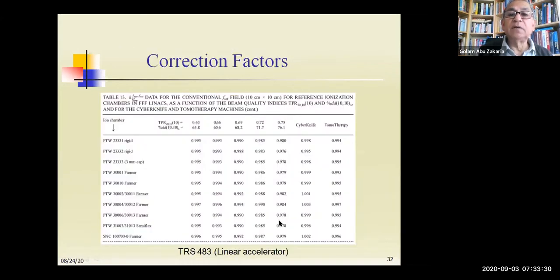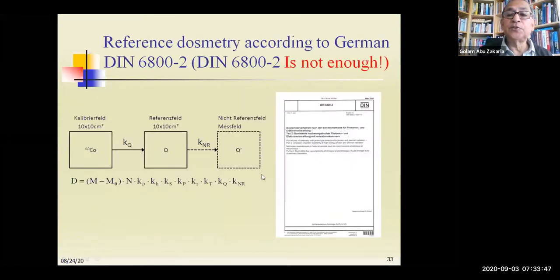So here are the correction factors. Here you see the correction factor for different types of chamber. Here is actually the TPR, and here is CyberKnife and tomotherapy. So you can use such types of protocol and put it in the formula, and you have the dosimetry. So I go to the German protocol. It is a little bit different, but we have shown they give the same result. This is the basic DIN norm from Germany, 6800-2.